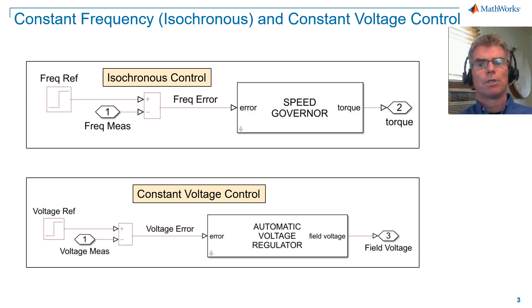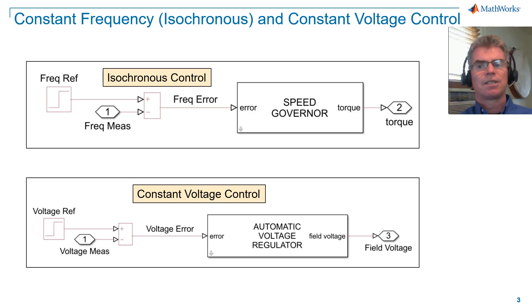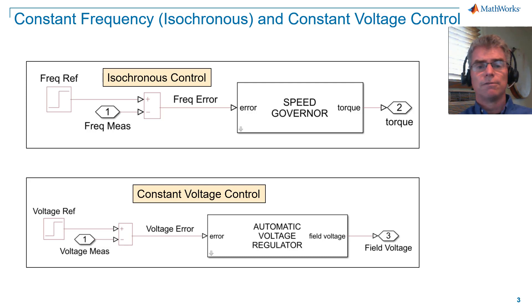The speed governor is responsible for regulating frequency, and an error signal that measures the difference between the desired frequency setpoint and the measured frequency is used to adjust fuel flow. The speed governor is designed specifically to reduce the frequency error signal to be as close to zero as possible. The automatic voltage regulator, or AVR, is responsible for regulating terminal voltage, and an error signal that measures the difference between the desired terminal voltage setpoint and the measured terminal voltage is used to adjust field voltage. The AVR is designed specifically to reduce the voltage error signal to be as close to zero as possible.